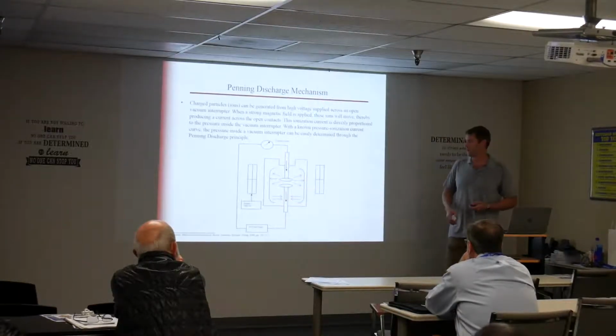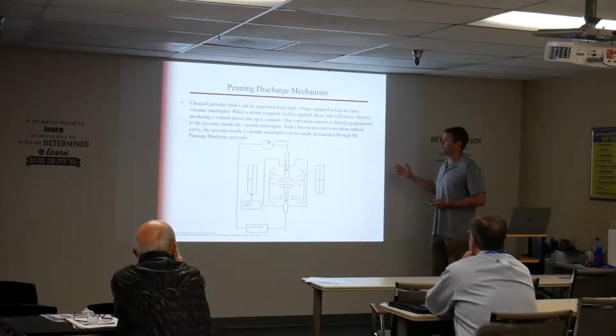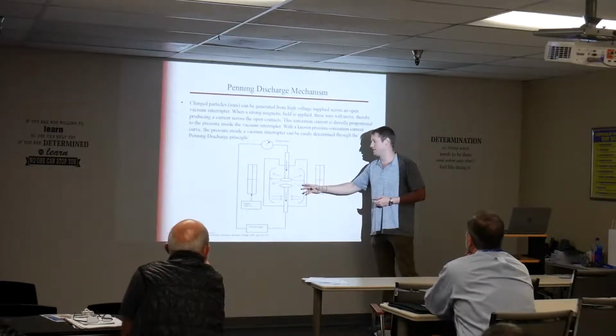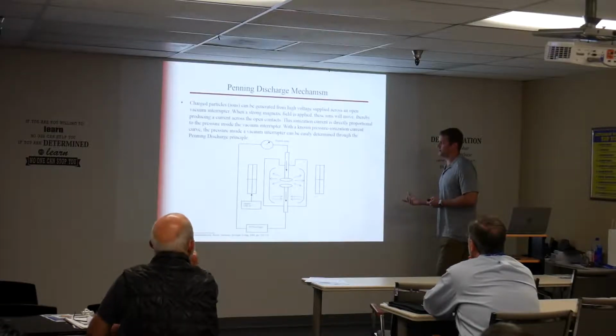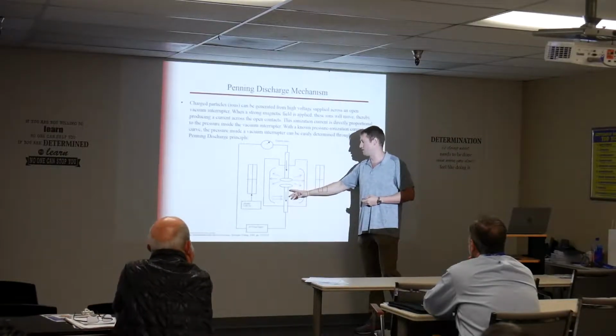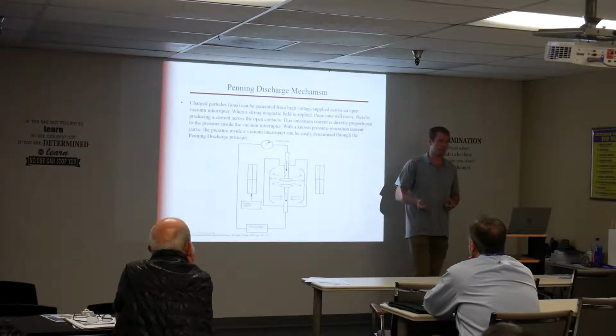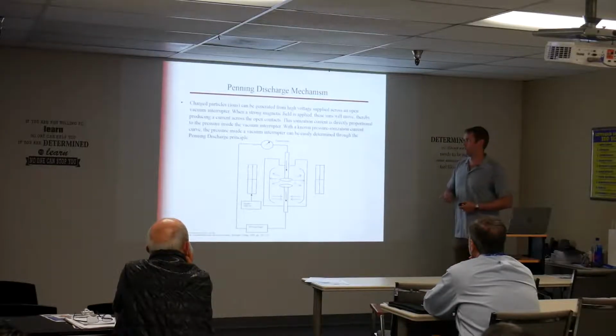So like I said, with our test, we can measure exactly how much gas is leaked inside this interrupter and tell you the exact pressure. Brand new interrupters should have very few gas molecules, so this current we're measuring can be really, really small, 10 to the -6 amps.